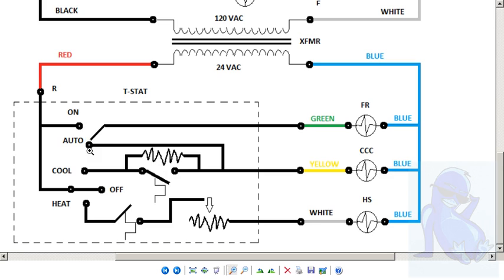When it is set on auto, your fan relay will not engage unless it's called for and it's going to be connected to your cooling circuit for that high-speed fan. On auto, you don't need this to come on in high speed unless it's connected to the cooling circuit. On heat, it will bring that low speed fan on because that low speed is already wired in. To do that, it's going through your sequencer.